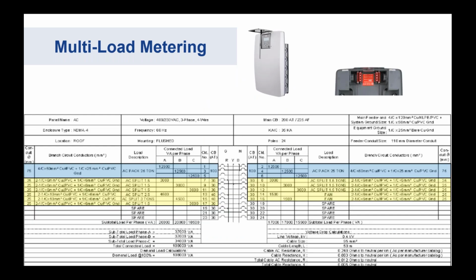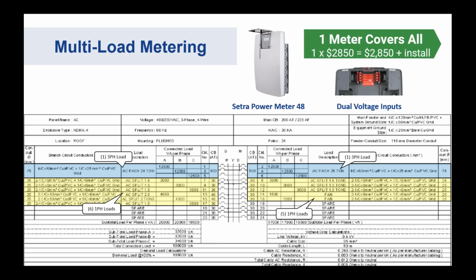Applying this approach to the same problem, we still had the same number of loads. We still wanted to measure 13 different loads, but now we could do it with 1 meter. So 1 meter with the CTs was around $2,850 for split cores. And now it's $2,850 plus install. So you're already saving over $6,000 right off the bat for the equipment, plus all the installation savings of not having to land those multiple wires.